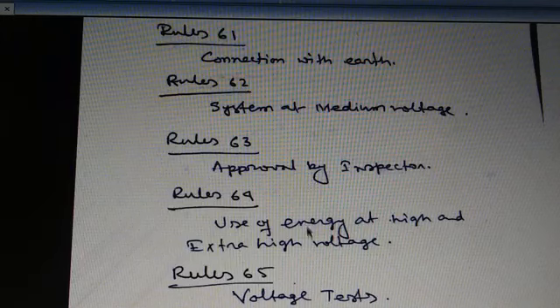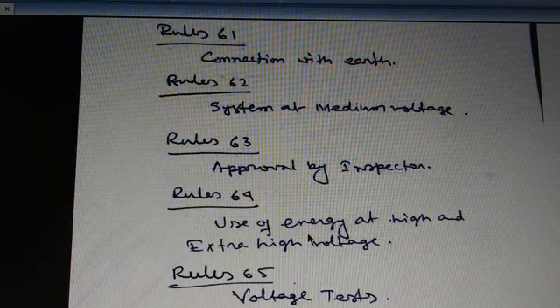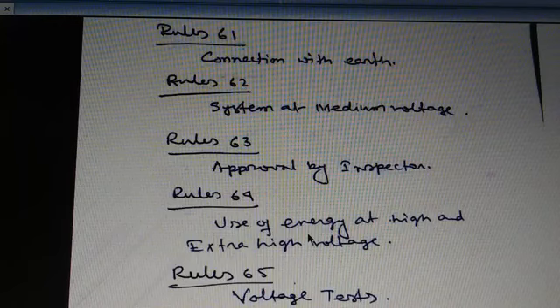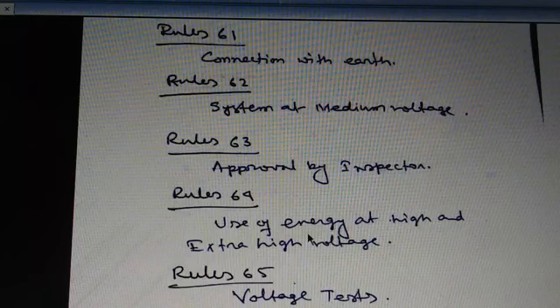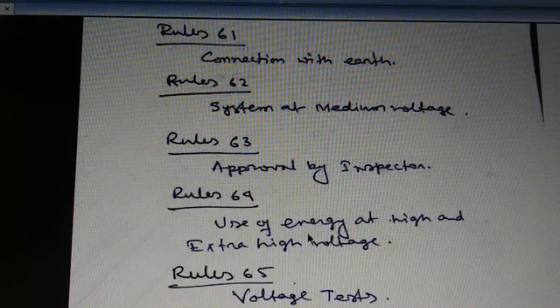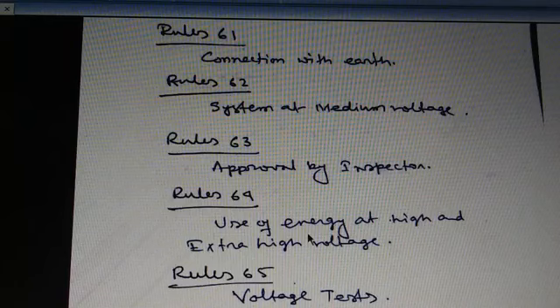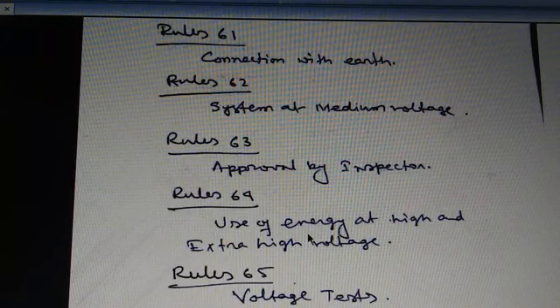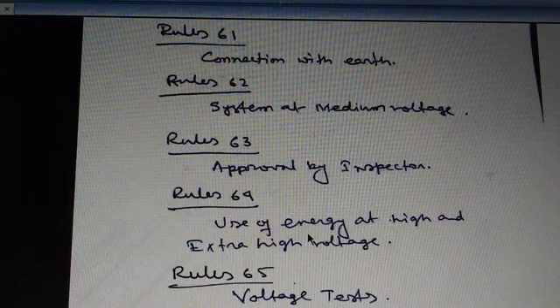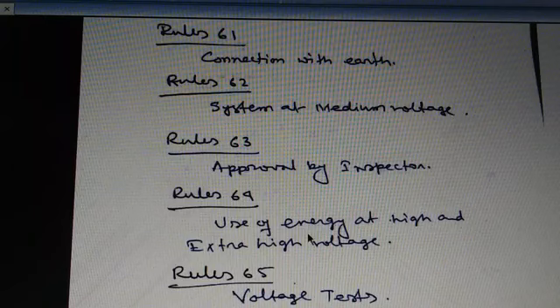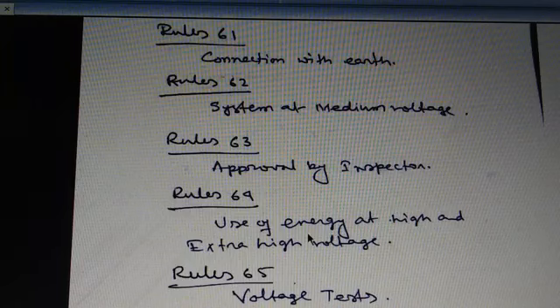Rule number 65, voltage test. High and extra high voltage electric supply lines, other than overhead lines, and apparatus of the supplier shall not be connected to a system for the purpose of supply or use of energy unless the insulation of the said electric supply lines and apparatus has withstood the test. Now, the test prescribed in this behalf by the electrical supply board or Indian Electricity Rules would follow. Next, in case where no such test has been prescribed, the continuous application between the conductors and also between conductors and the earth during the period of 1 minute of such test voltage by sub-rule 2.